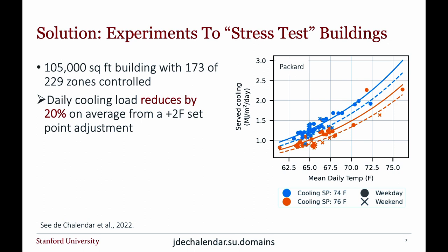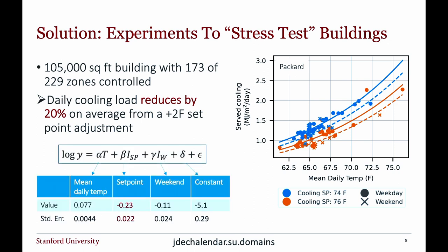Okay, so when I do this for the Packard building, I measure an impact of 20%. How do I do that? I estimate a linear regression for a cooling load, y, as a function of outside air temperature, the set point change, whether it's a weekday or weekend. I can control for other things.